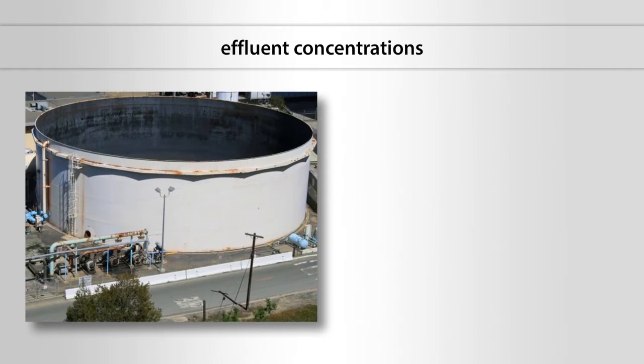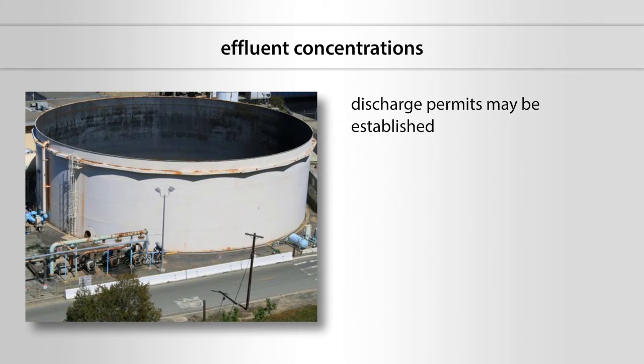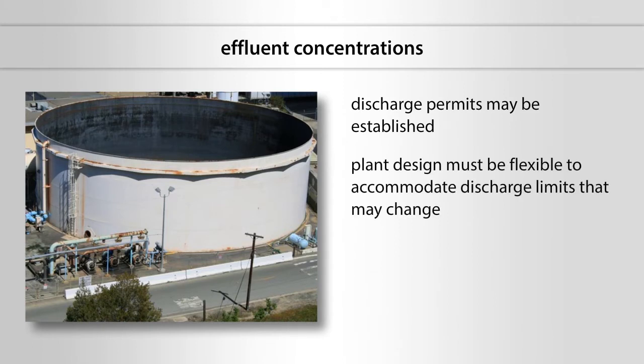Effluent concentrations follow a similar scenario. Discharge permit limits may already be established, which provides a solid base for the required treatment performance. However, discharge limits are frequently being established and or negotiated concurrent with the design process. In that case, the treatment plant design must be flexible enough to accommodate discharge limits for certain parameters that may change late in the design process.